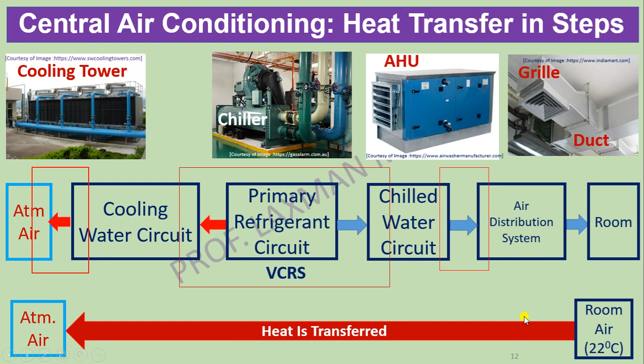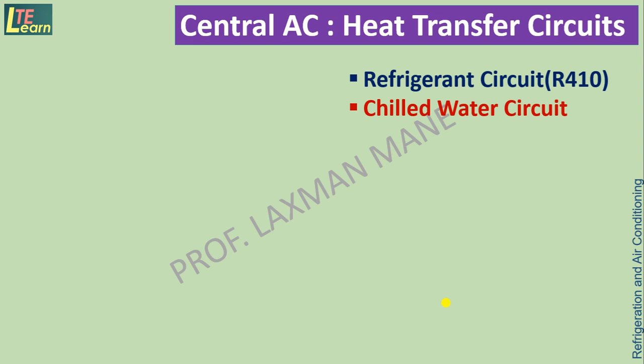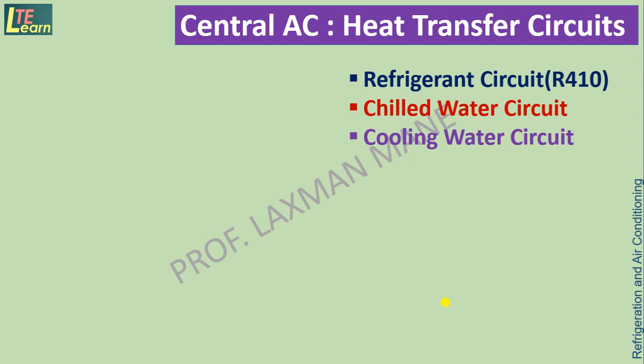In a central air conditioning system, there are mainly three types of heat transfer circuits. The refrigerant circuit contains refrigerant R410A, the chilled water circuit contains water as a secondary refrigerant, and the cooling water circuit carries water for cooling of the condenser. These three circuits form a device called a chiller. The major component of the chiller is a VCRS system, which consists of a compressor, condenser, expansion valve and evaporator. This is the refrigerant circuit. It produces very low temperature at the evaporator and high temperature at the condenser.